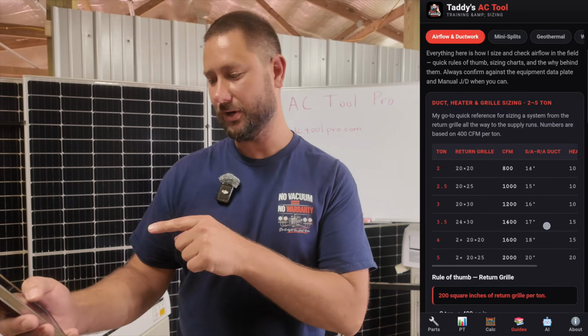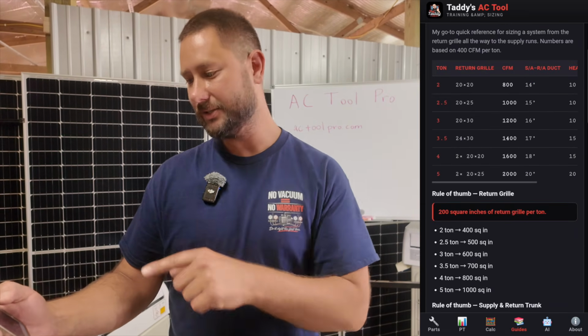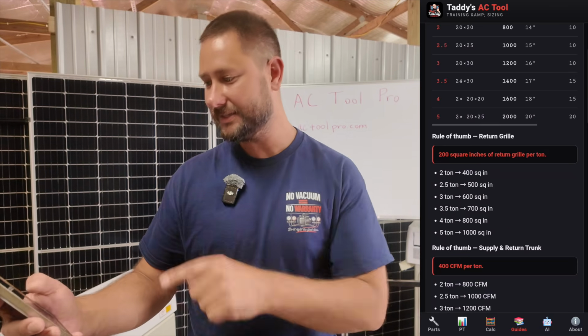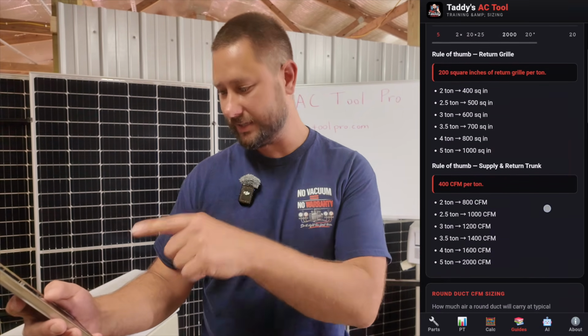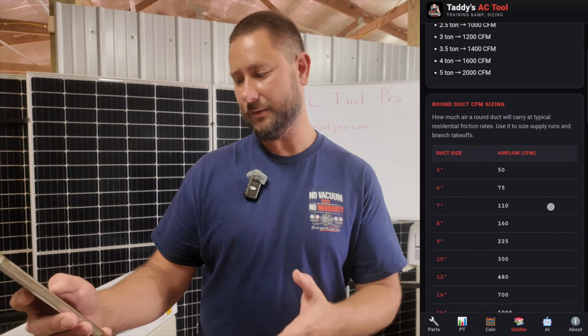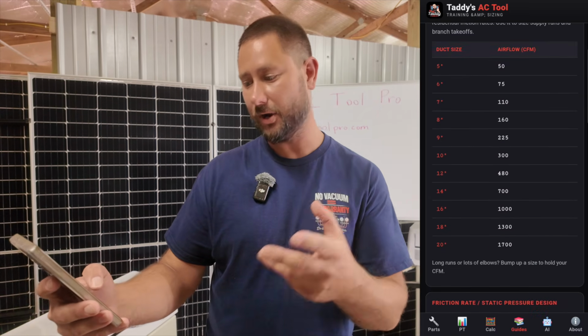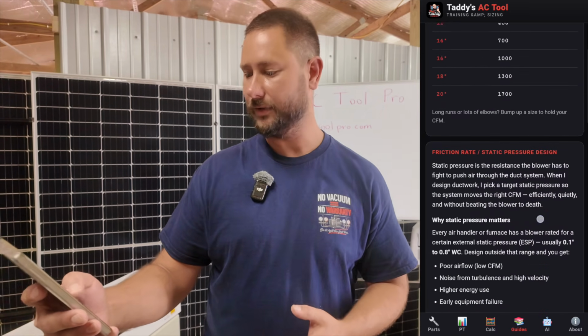So let's dive in. The first guide, probably the most requested, is airflow and ductwork. It's nice to be able to just scroll down and see, oh, it's a 3-ton unit, it needs this size return grill, it's got this CFM, we can do this many vents, and we can look at the round duct size, maybe our branch runs, look at the airflow, and then learn about friction rate and static pressure, and then we can look at the different statics.